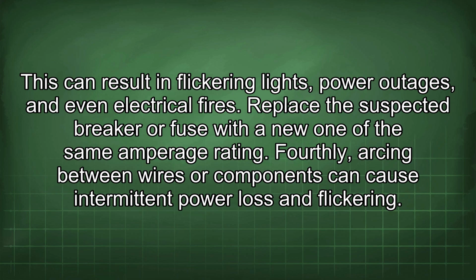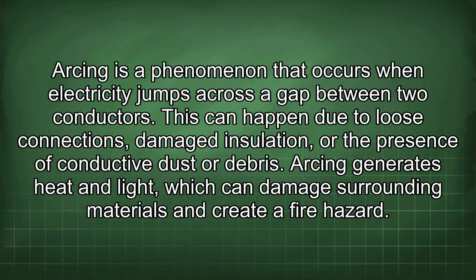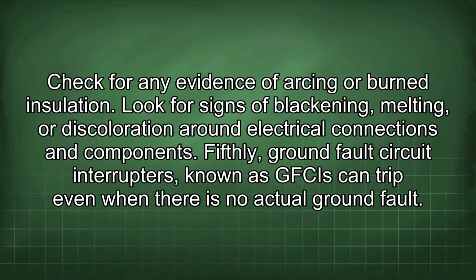Fourthly, arcing between wires or components can cause intermittent power loss and flickering. Arcing is a phenomenon that occurs when electricity jumps across a gap between two conductors. This can happen due to loose connections, damaged insulation, or the presence of conductive dust or debris. Arcing generates heat and light, which can damage surrounding materials and create a fire hazard. Check for any evidence of arcing or burnt insulation. Look for signs of blackening, melting, or discoloration around electrical connections and components.